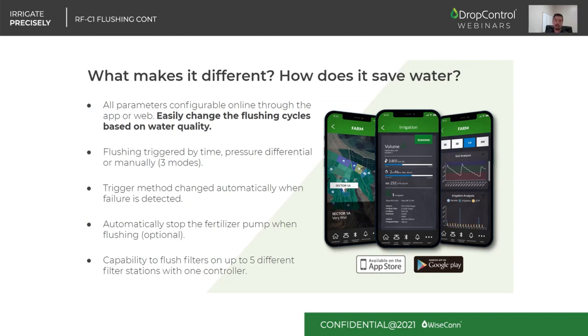You can have them all if you want. So in case you want to have a backup plan, you can have more than one sensor connected, and then at any moment, we can swap or switch which sensor is going to be the reference to trigger the flush cycle. Or you can trigger any cycle manually. And whenever we reference manually, it's not only locally at the site, you can manually start it remotely. So the trigger method is also changed automatically when a failure is detected.